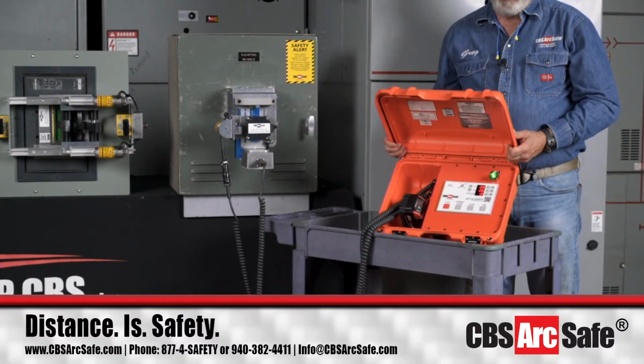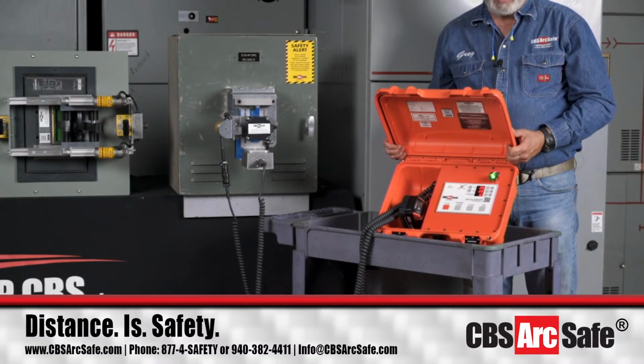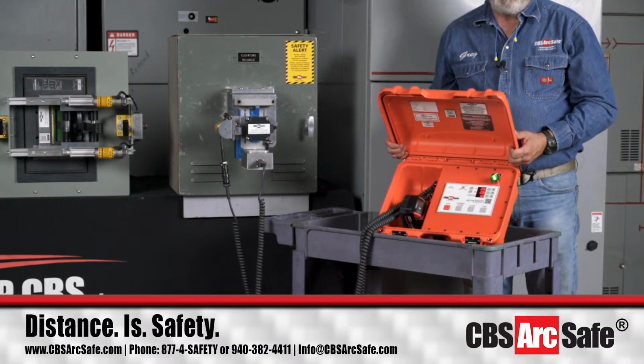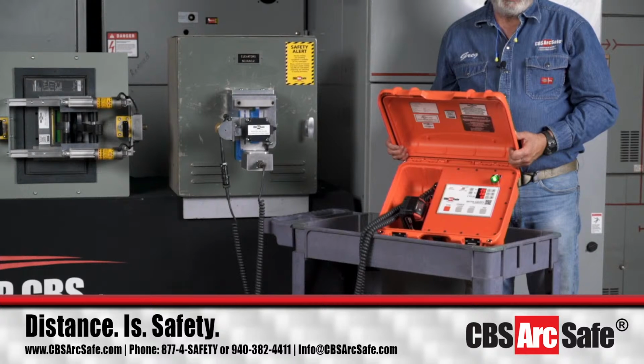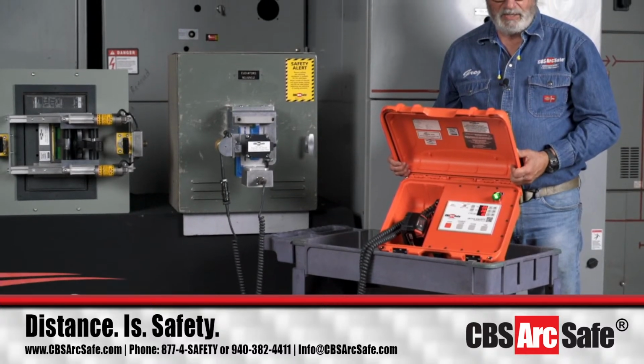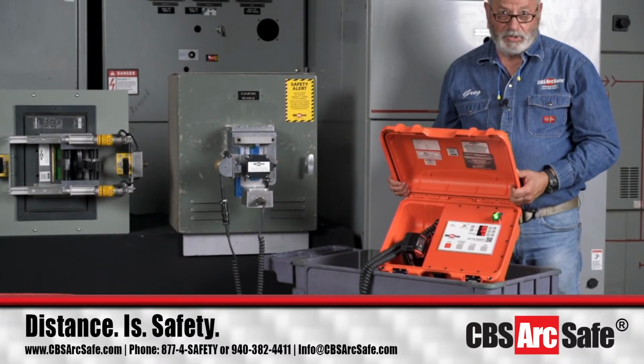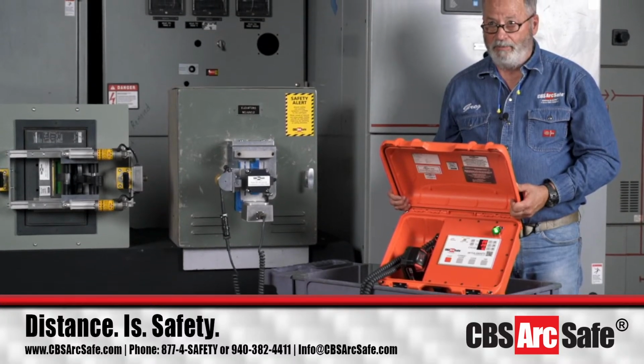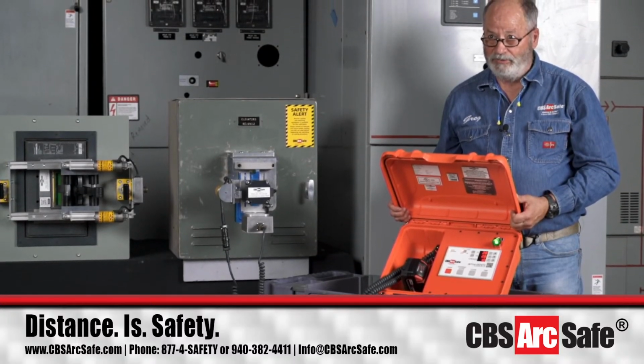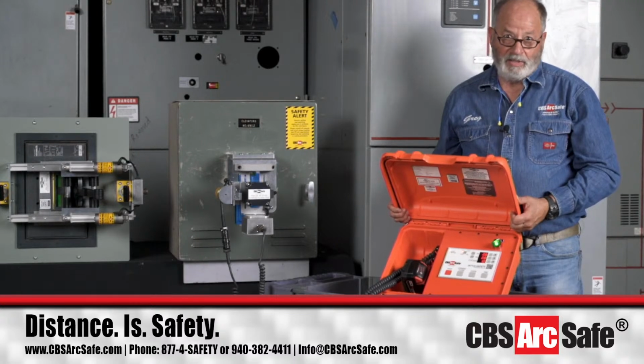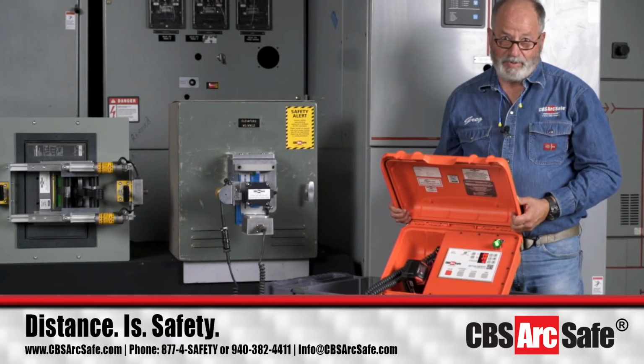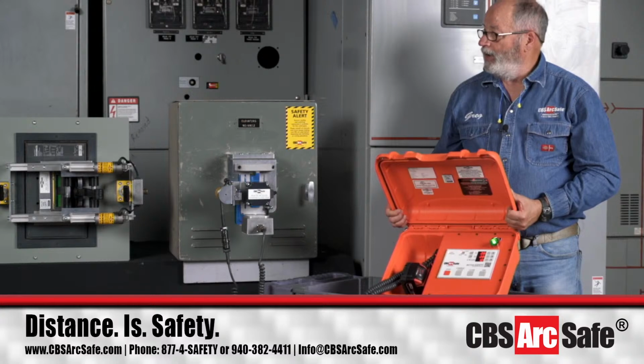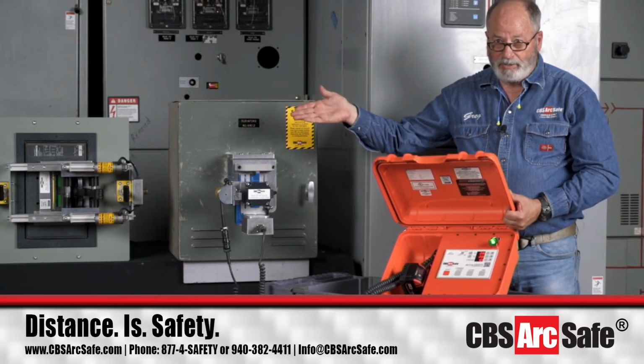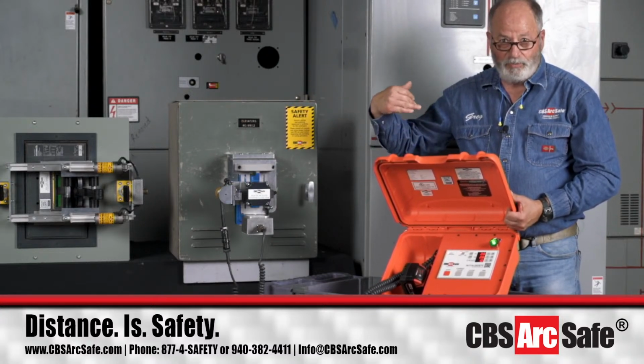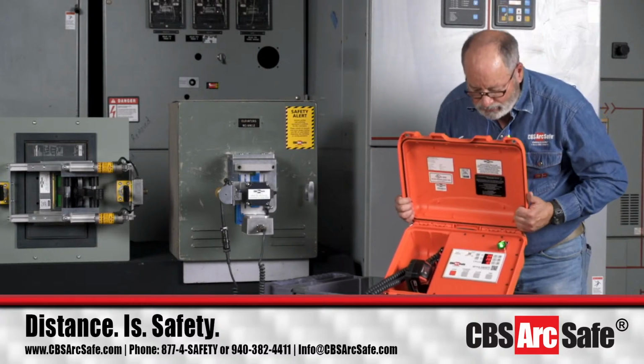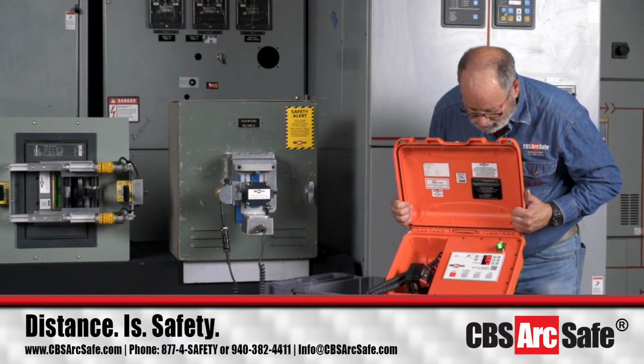Now, all those T1s and T2s are how we set up our systems to operate. So if you have any of our charge-close trip actuators, it'll say T1, T2 cycles. A Magnum DS will be like 5 cycles with a different time on it. Something for a Square D Masterpact, something else. For an electrically operated DS breaker, 9 strokes. For a manually operated one, 1. All those things are on the label that comes with the piece of equipment.